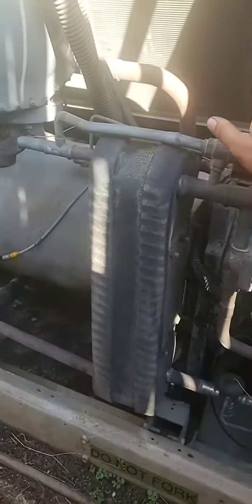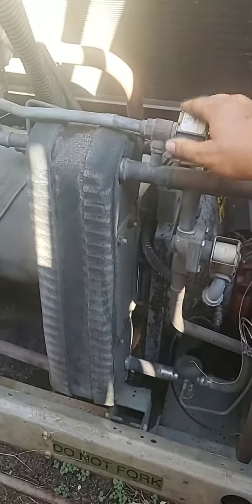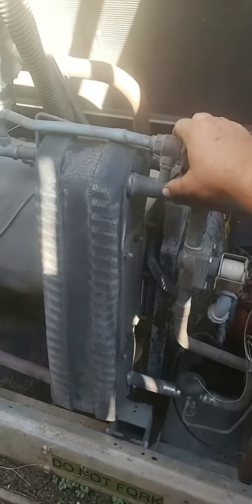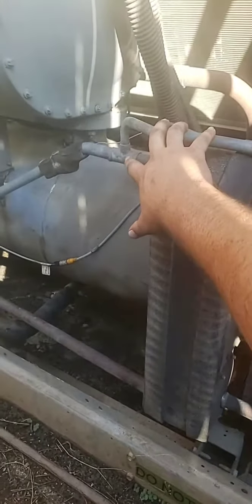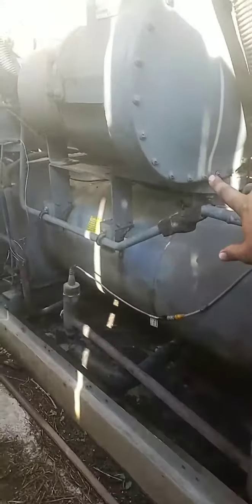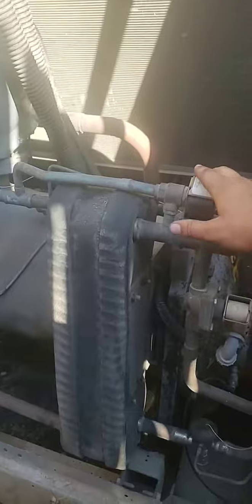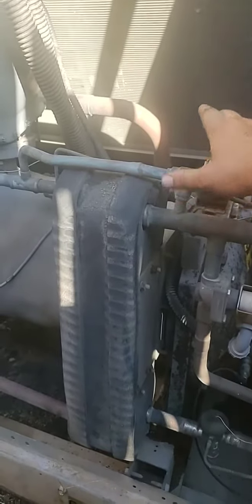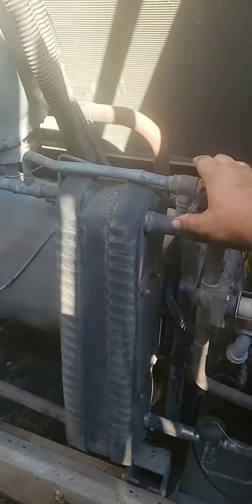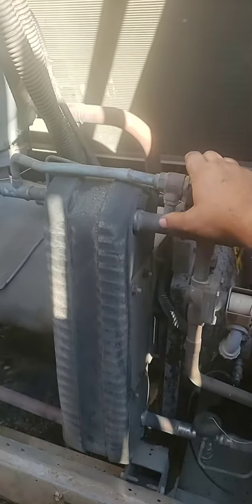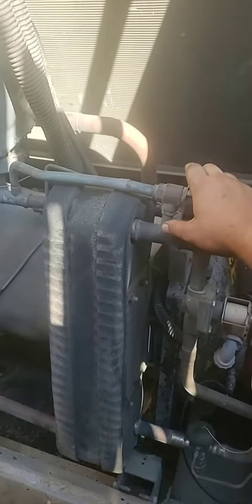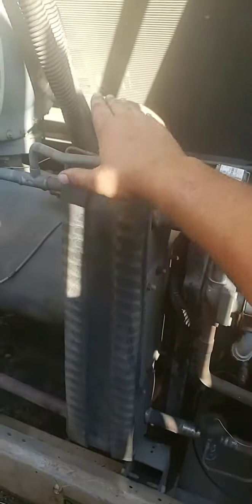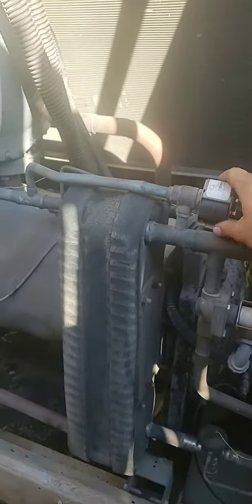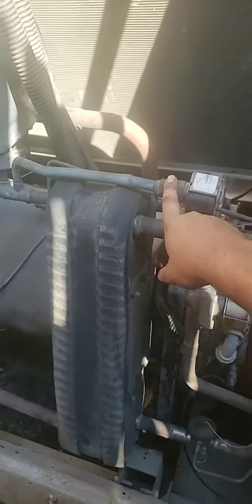So what this relay or the solenoid is doing is it is firing and dumping liquid straight into that line. Now keep in mind, by the time it reaches the motor, it's going to have boiled off. But this is how they're actually cooling the motor. The motor in this one is liquid injection cooled. It is not suction gas cooled. So that's a very critical thing to understand. So if this valve is ever not firing, or you're not seeing this line here start to sweat while the motor is running, you've got a definite problem. So like I said, this is your motor cooling circuit.